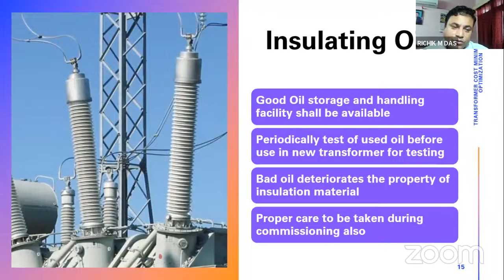This will give the transformer a long life. Periodical testing of used oil is important, as manufacturers generally use oil testing since this oil first goes into the transformer and is impregnated throughout the insulation. So these oil parameters should be very good, otherwise the transformer life will be greatly impacted. Bad oil deteriorates the insulation material's properties. So during commissioning, we should take proper precautions when new oil arrives, on how to process and handle it, so that oil parameters do not deteriorate.